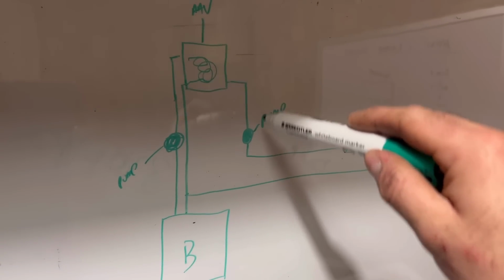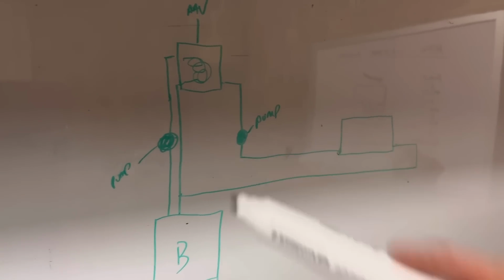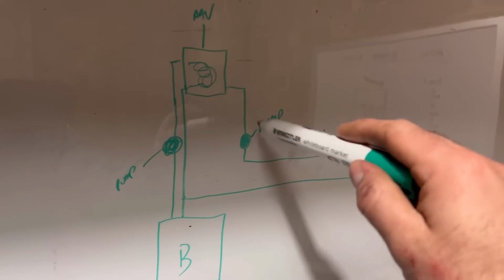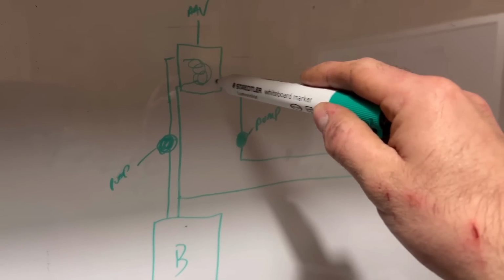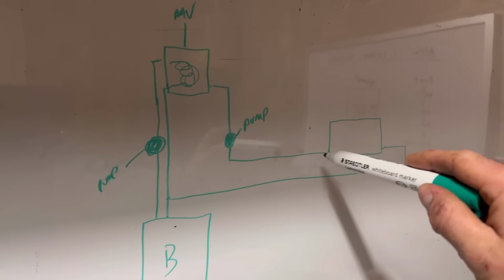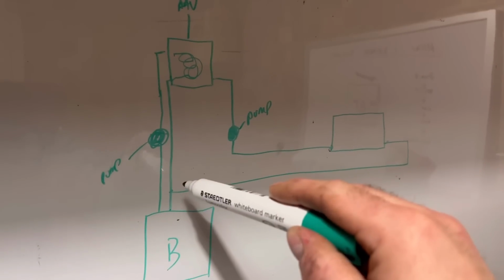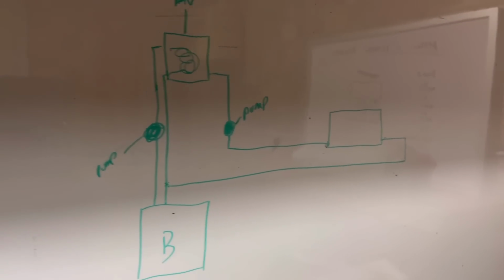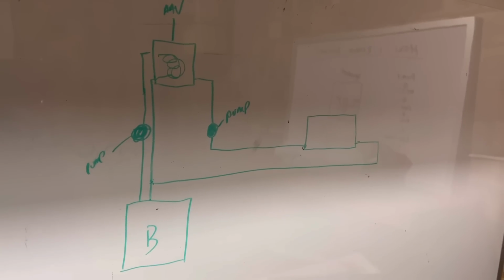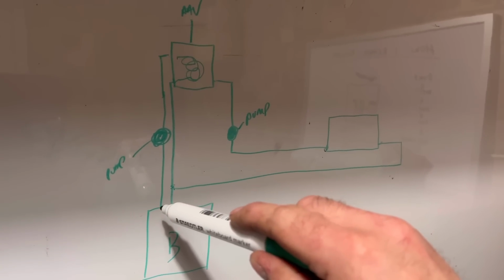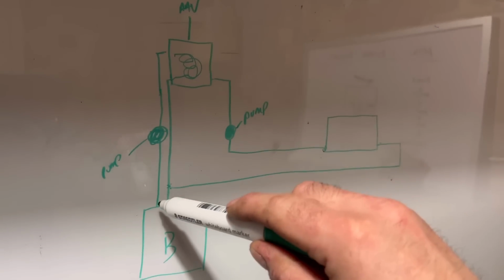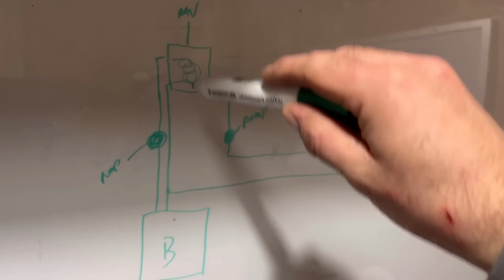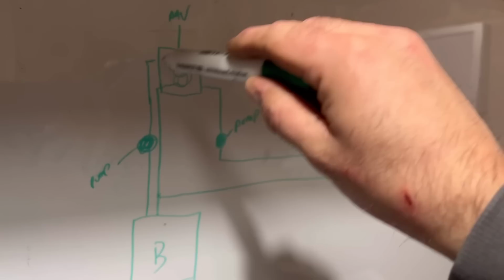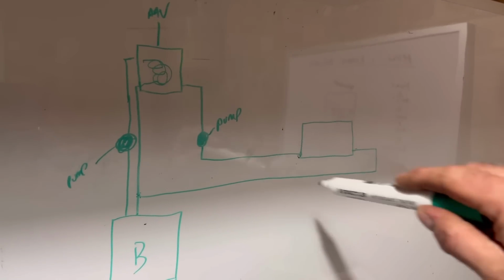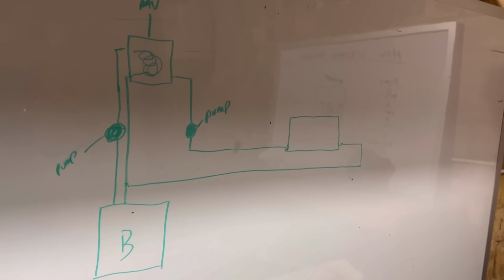And then what this side does - it's got a pump on there as well, all linked in at the same time - while the pump's running, this side pulls the heat out from there, takes that off and feeds all your radiators, then comes back and links back in here. The idea behind it is very similar to a low loss header really, that the boiler isn't doing as much, it's not having to work very hard. So the pump on this side is literally just circulating heat round this loop, and this other pump is taking it and doing this loop here. So in effect, they are quite good.